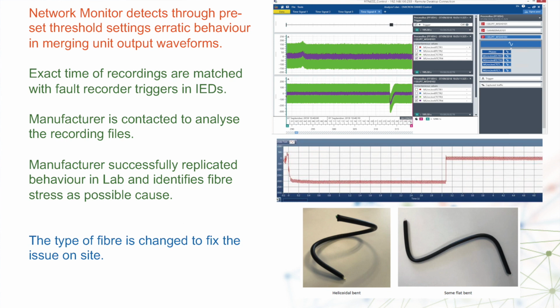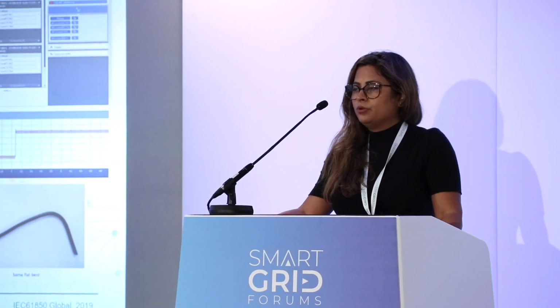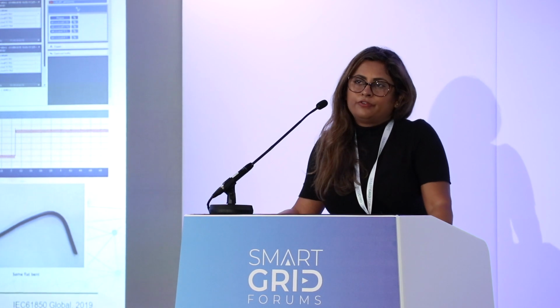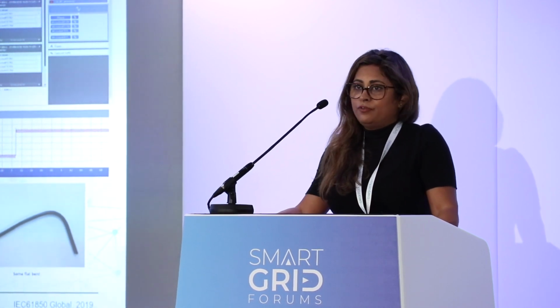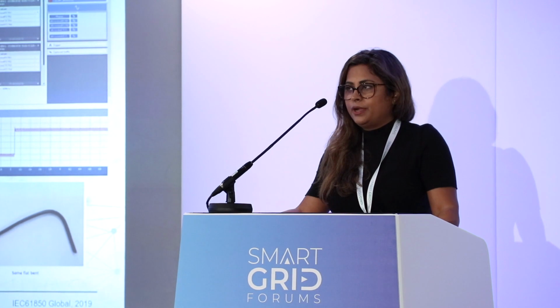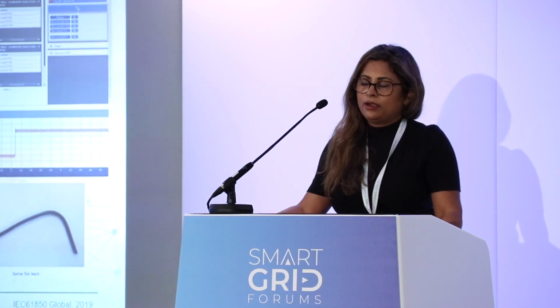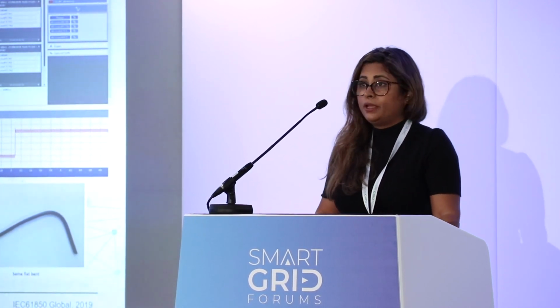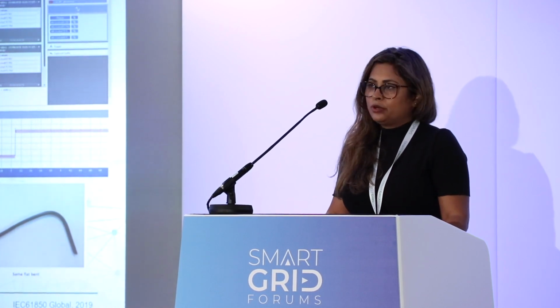But what we created in that process is, the armored fibers are quite tightly wound around the fiber, the armor cable, we bent it. A couple of times, everything was fine, we commissioned the system, no problem. Then a couple of times I would notice that the fault recorders of the relays were picking up a signal or a fault which was not on the network. So we compared this with the conventional system, because the system runs in parallel with the conventional system. That behavior is not there on the conventional system. So what could go wrong?